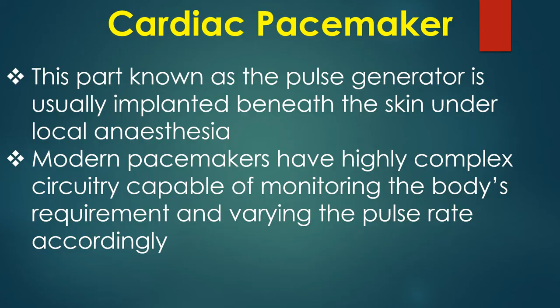Modern pacemakers have highly complex circuitry capable of monitoring the body's requirement and varying the pulse rate accordingly. They are also communicating devices which can transmit the stored information to a device known as a programmer kept over the surface of the skin. The programmer can interrogate the pacemaker to retrieve important information regarding pacemaker function and malfunction. Latest programmers can send the data to a server over the internet, making it feasible for the specialized physician to evaluate complex pacemaker function sitting in another country or continent.